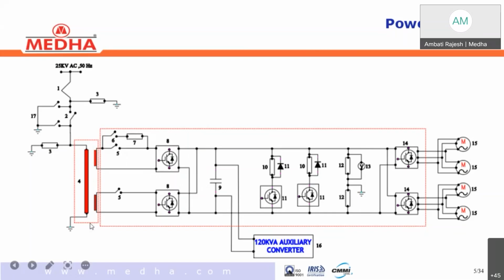During braking, this traction transformer acts as a step-up transformer and converts that into this 25 kV supply, and the system continuously measures the OHE voltage and a little higher voltage will be generated in the primary. So obviously current starts flowing from higher potential to lower potential. In this fashion, the current will be fed back to the OHE. This phenomenon we'll call regenerative braking.